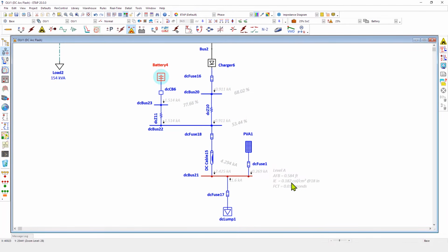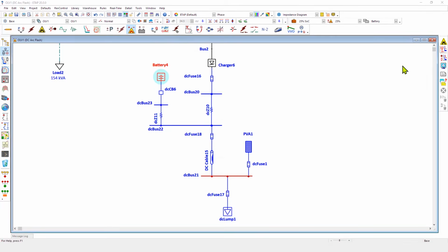We can then go ahead and follow the same steps and change our state of charge from 25% to 50% and observe how these numbers are changing. We can see that the incident energy increases slightly and the fault clearing time remains the same. And once we reach a value of 100% state of charge, we can also observe that the incident energy increases while the fault clearing time remains the same. And this is because as the state of charge is increasing, the fault current or the arcing current is increasing while the clearing time remains the same for this protective device.